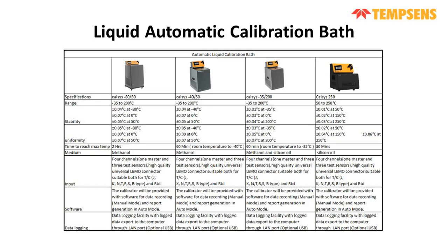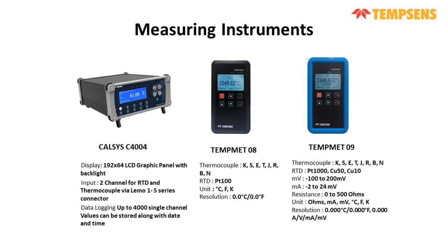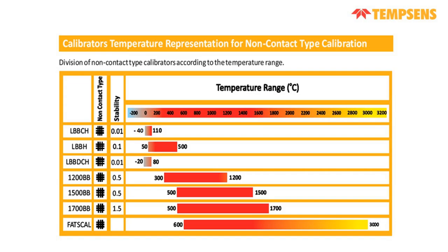So these models are also available in the automatic AutoCal system, and that comes with a digital display, and that can be used for all types of thermocouple and RTDs. Comes along with the software for the data transfer and everything. These are the measuring instruments we have: CALSYS C4004, TEMPMET 08, TEMPMET 09. Moving on to the non-contact type calibration.